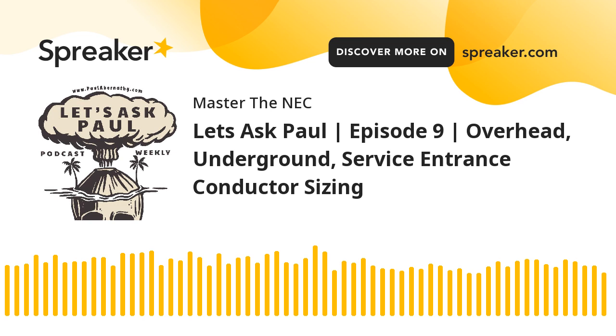However, under exception number 5, it says the overload protection for a 120/240 volt, 3-wire, single-phase dwelling service shall be permitted to comply with the requirements of 310.12. Notice it says service. Again, this is only going to apply to the service, because obviously we're in 230, so we're talking about services. So this is what allows us to have that 83% rule, and it's 83% of the service rating in our case, since we are talking services.